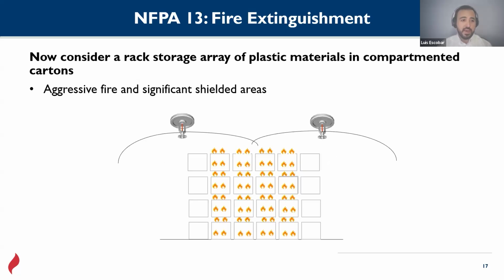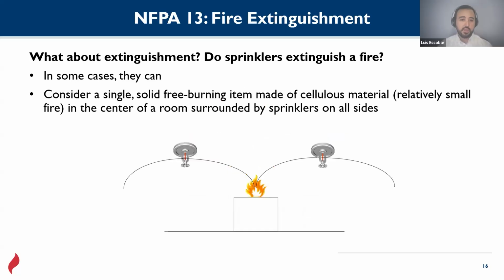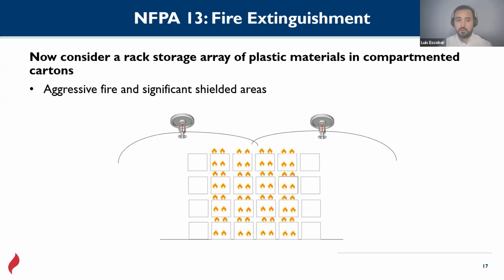But what if we have a rack storage of combustible material, which can be plastic? We all know plastic is very, very flammable, and it's stored in carton boxes, for example. Obviously, there are schemes of protection for all these applications, but what I mean with these two slides is that the fire sprinkler system for the first one will be totally different from this one, because for starters, this will need more water for obvious reasons. There are a lot of carton boxes set on fire.